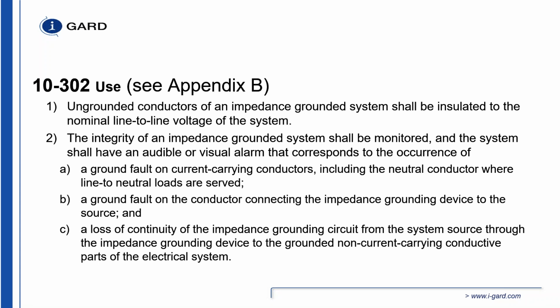So 10-302, ungrounded conductors of an impedance grounded system shall be insulated to the nominal line-to-line voltage of the system. This goes without saying. Up to 4160 volts, up to 5001 volts, the insulation on cables has to be 100%. There is no requirement to have cables at 173% when you have a fault that's on your system for greater than 1 hour. So you have to have conductors that are insulated to ground equivalent to phase.